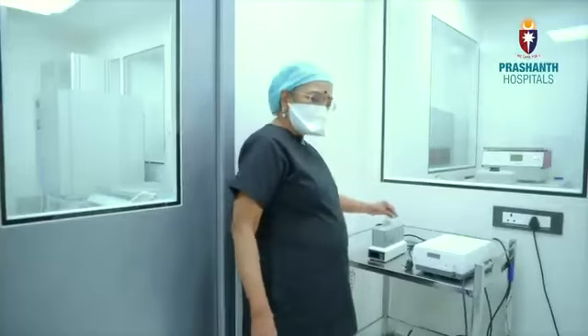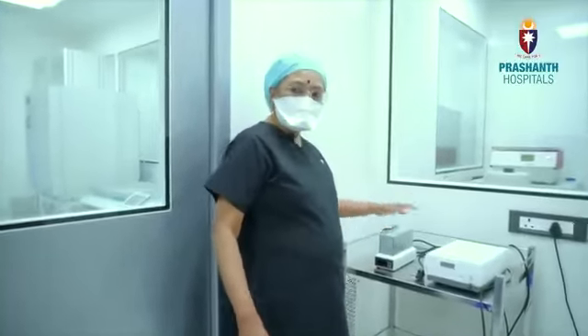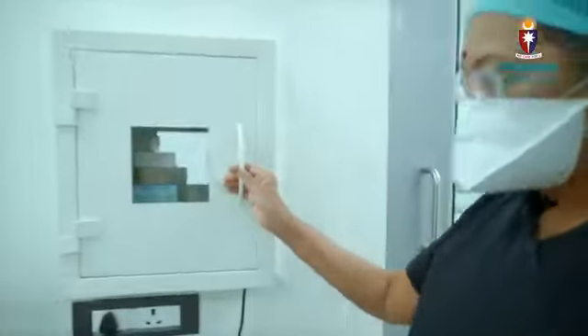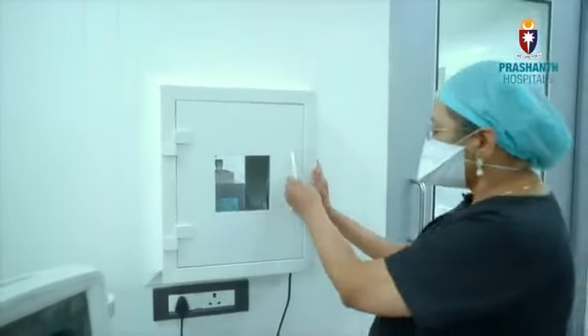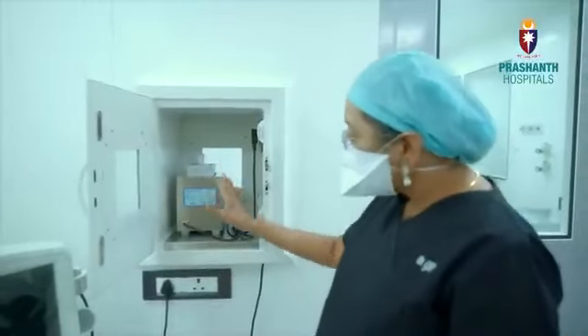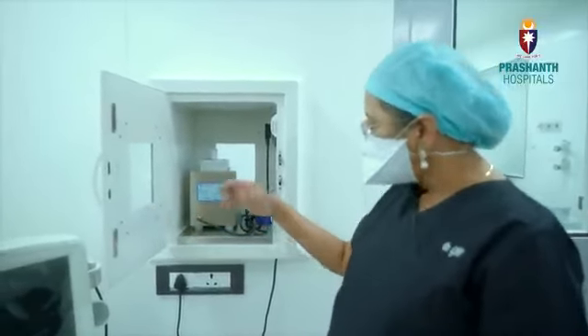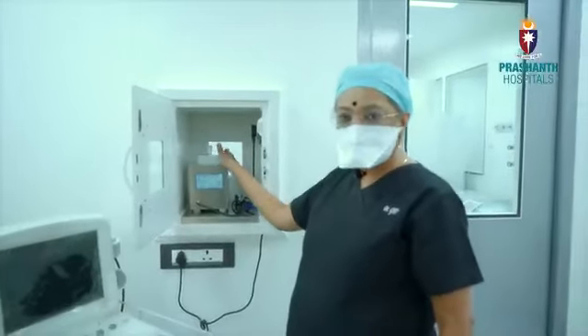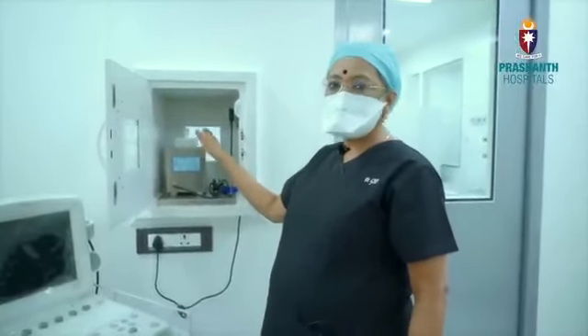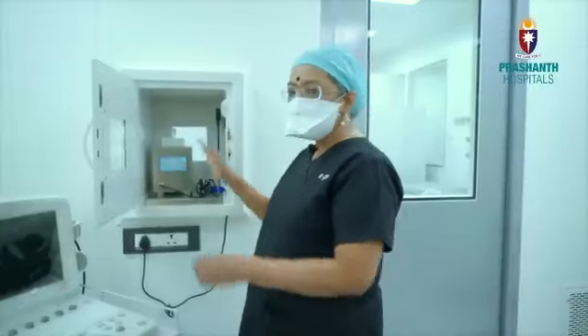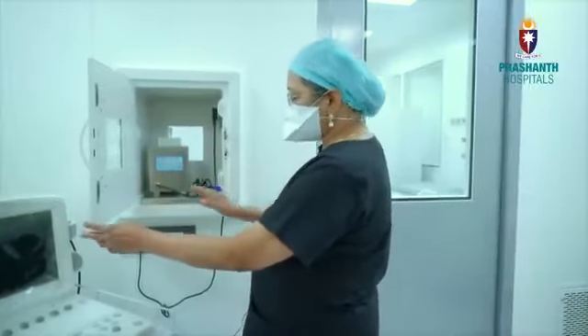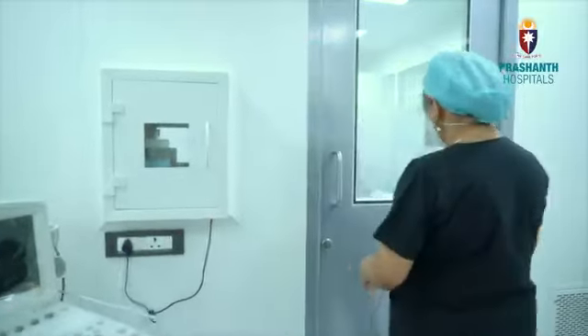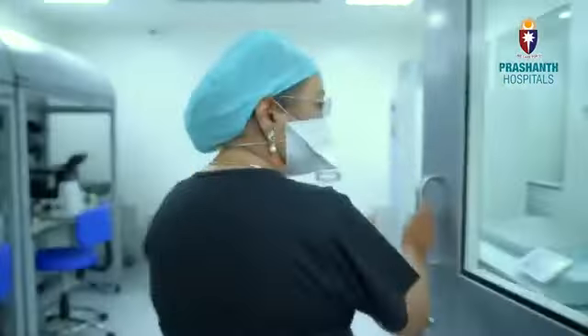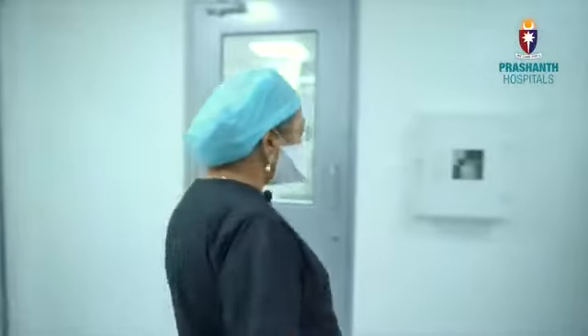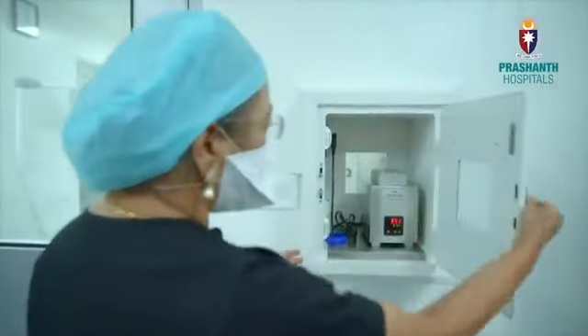The eggs are collected, but you keep it here for about 3 or 4 tubes or till you finish one patient. Then this warmer goes into the hatch. Now this hatch is a very important concept because once again it is a closed space. If you open it, then all the tubes in the warmer are kept into this digiblock, and this digiblock once again maintains temperature at 37 degrees centigrade. So all the time the follicular fluid is at 37 degrees centigrade. Now only when I close this door will... now this is an alarm going off. So the outer door is now locked. Automatically it's locked. Nobody can enter the lab till I close this door. So once again, this door opens only when that side is closed.